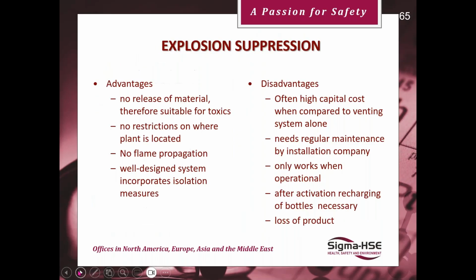So, advantages: no release of materials suitable for toxics, no restrictions where the plant can be located, no flame propagation, well-designed system. It incorporates isolation measures. Disadvantages: often a high capital cost when compared to venting. Needs regular maintenance by the installation company.